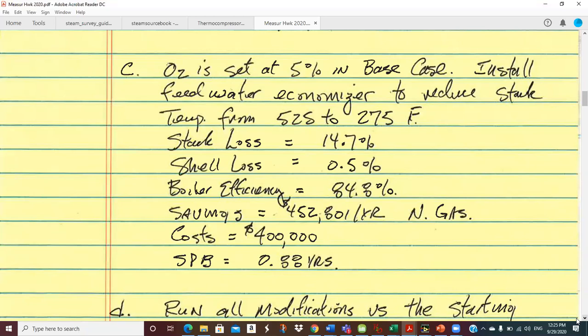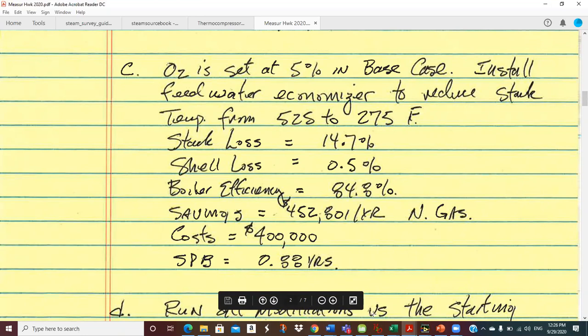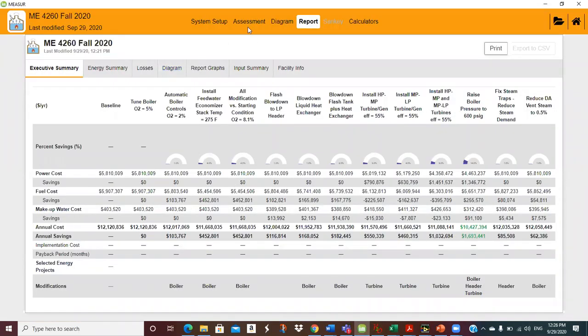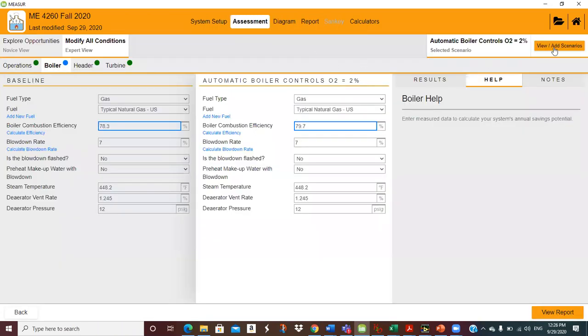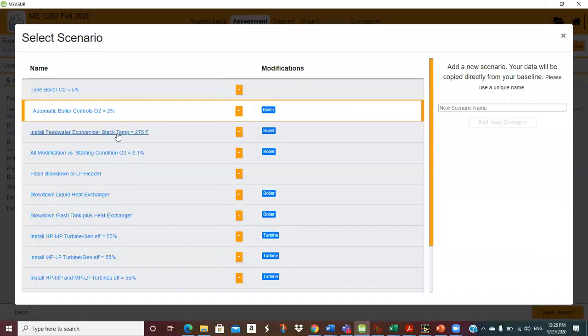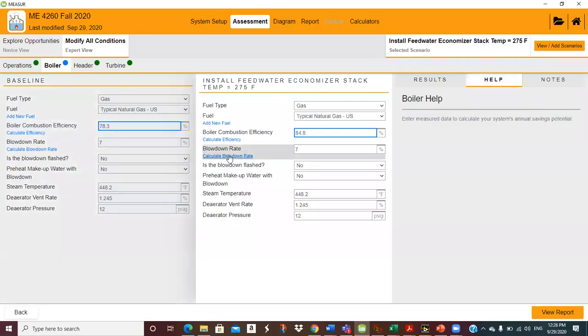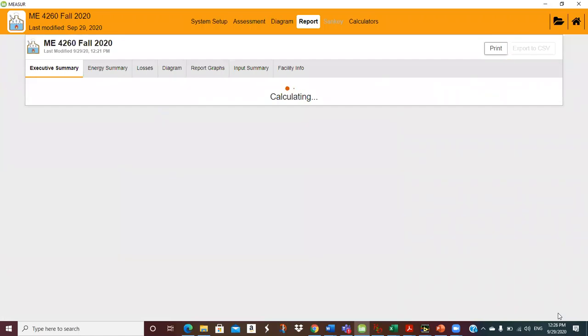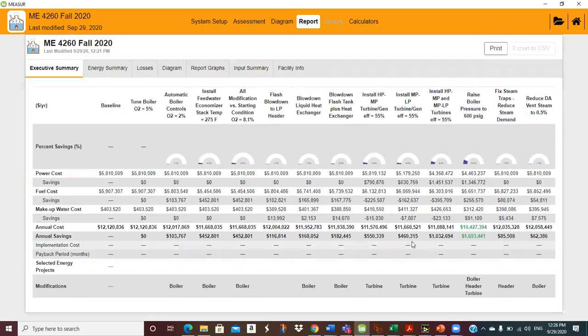That's a pretty significant improvement. The shell loss with that — the boiler efficiency is now pushing 85%, which is pretty close to as good as you're going to get on natural gas without a condensing economizer. For an industrial steam system, 84.8% is pretty darn good — nothing to sneeze at. The simulation came back at $452,801 in savings.